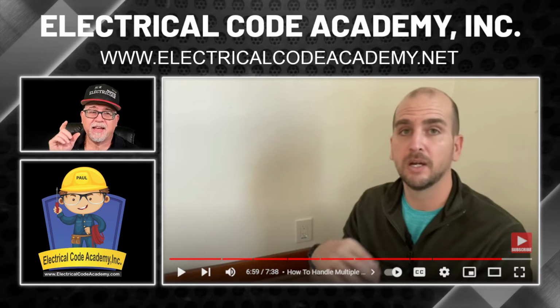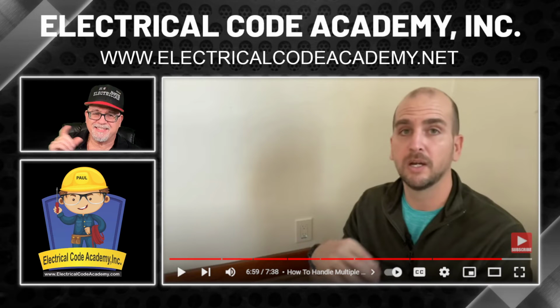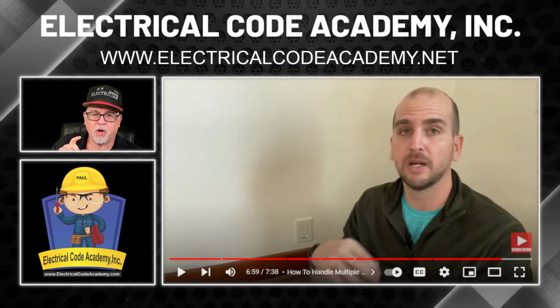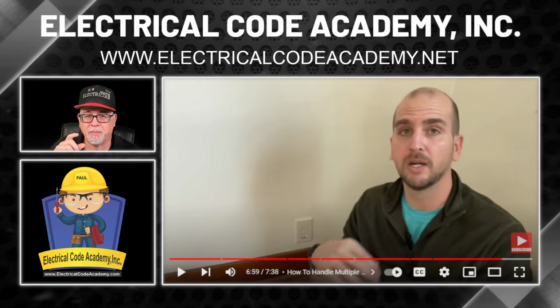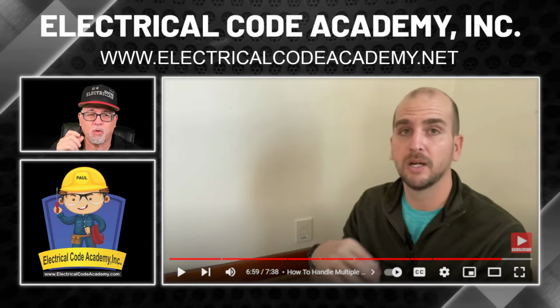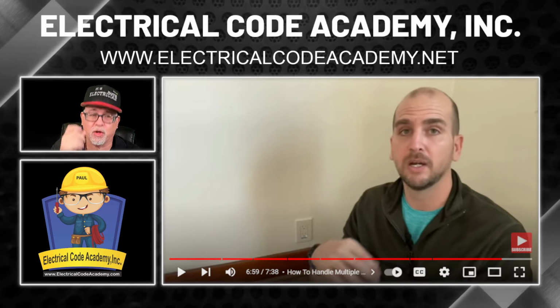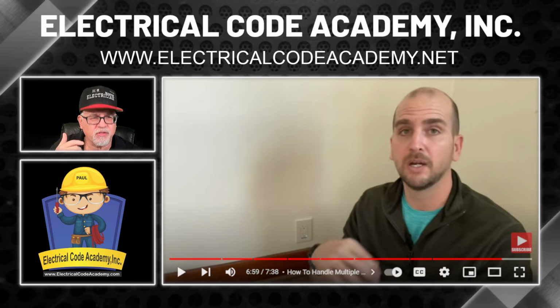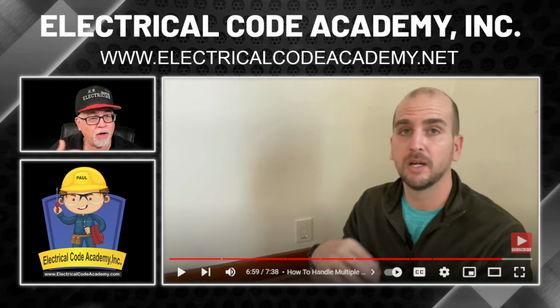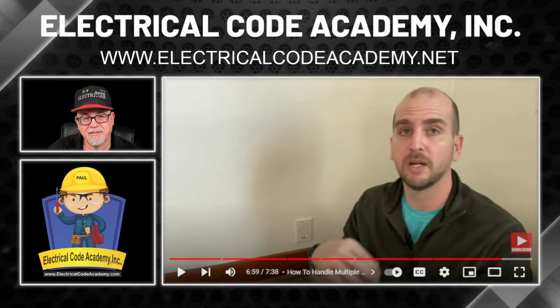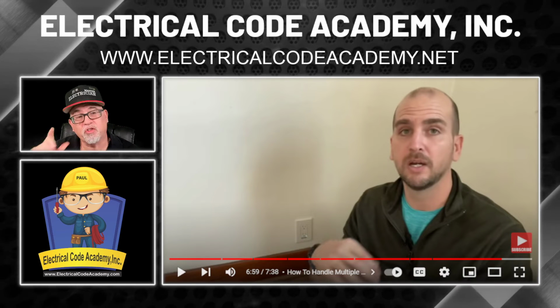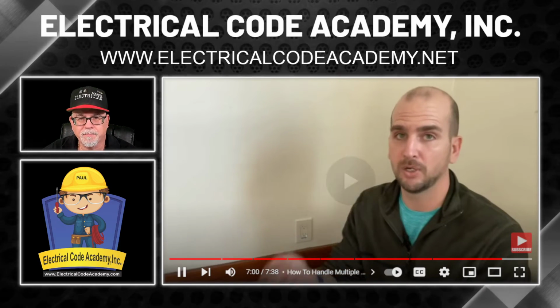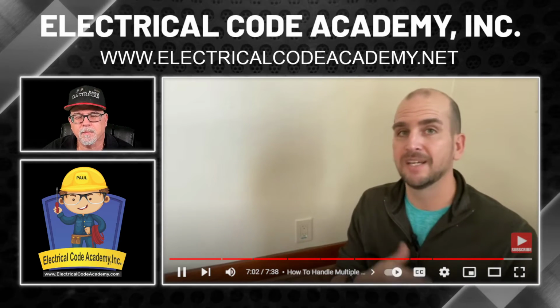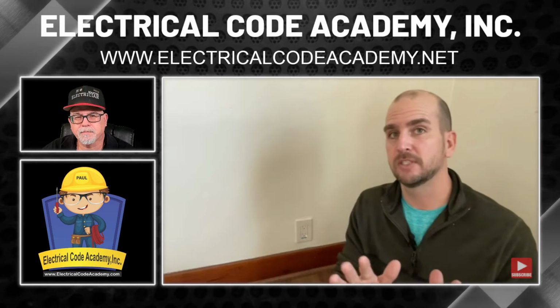Now remember, when he's saying normal receptacle, folks, we're talking about today. So this would be the receptacle called the grounded type. Means it's going to be three prong, and it's going to have a green equipment ground terminal on the device. Okay, that's when he says normal receptacle. They're called grounded type receptacles today, right? Three prongs for short, as opposed to a GFCI.